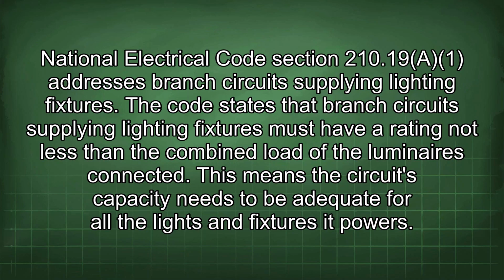National Electrical Code Section 210.19(A) addresses branch circuits supplying lighting fixtures. The code states that branch circuits supplying lighting fixtures must have a rating not less than the combined load of the luminaires connected. This means the circuit's capacity needs to be adequate for all the lights and fixtures it powers.